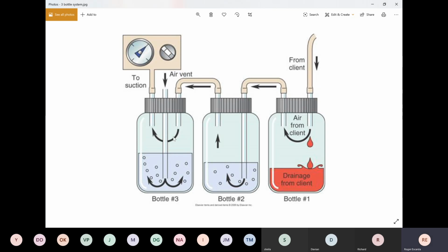However, there are consequences here. If we put this suction up too high, what will happen to this water here? You have tubes here. So the suction, there's a tube here only this length of tube. It does not dip into the water, so it will not suck. It can't suck, just like you guys, if you have a straw in your drink, but then the straw cannot reach the water level.